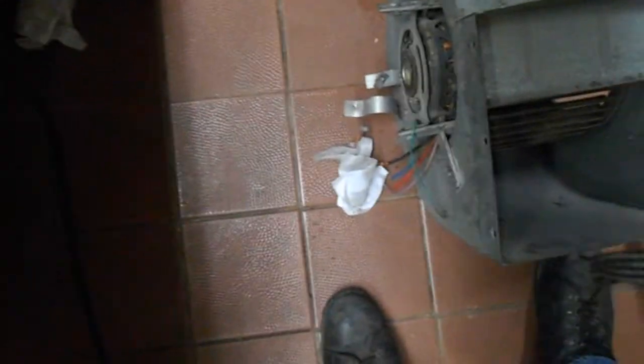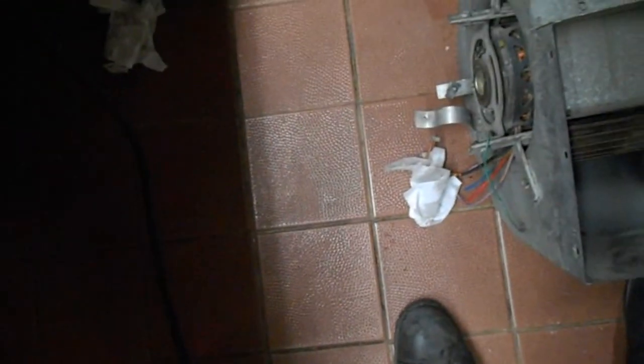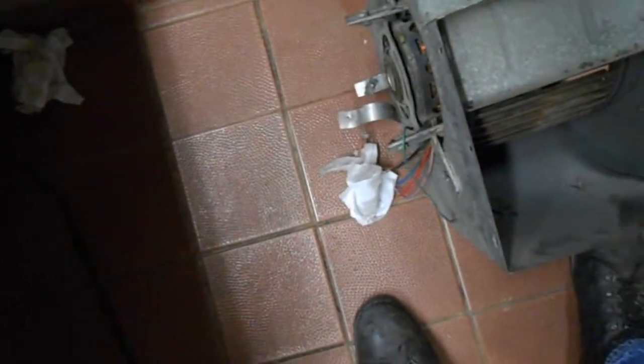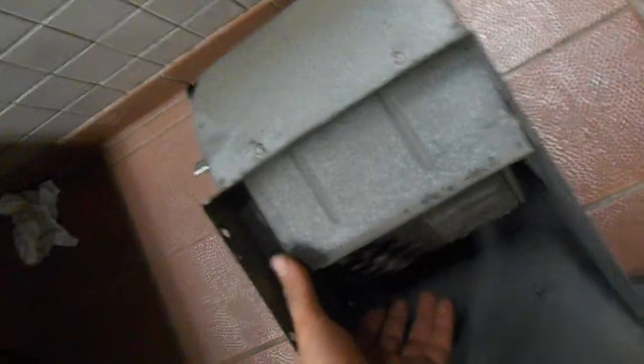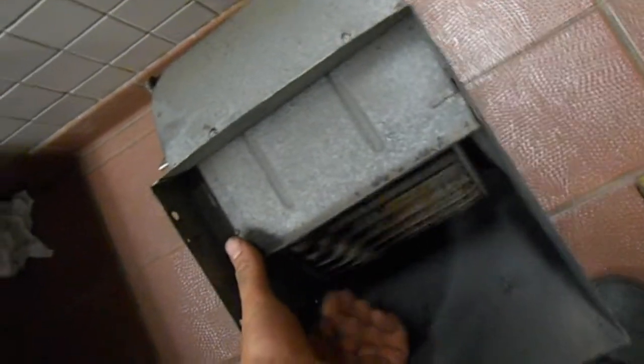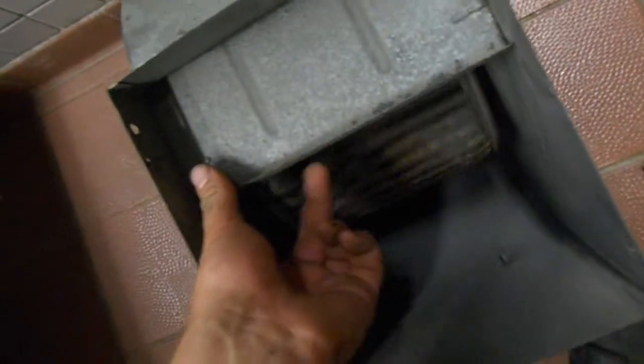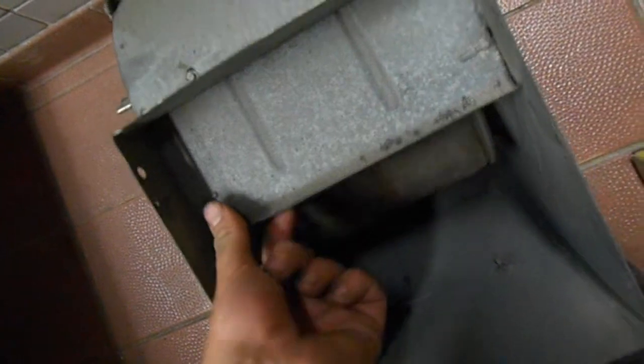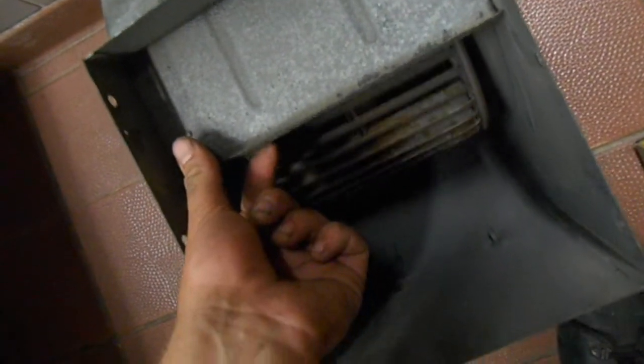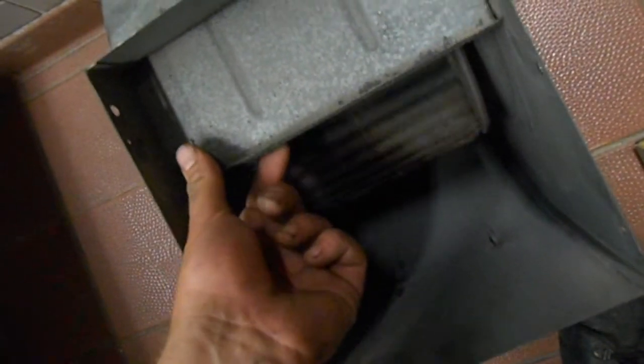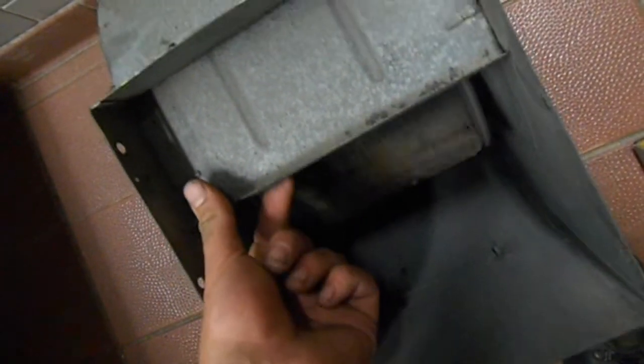So, this fan motor, it's not grounded either, which is kind of what I expected. Checked it with the megohmmeter even, and it's fine. But as you can see, the bearings have gone. So, this motor has mechanically failed. That should be spinning nice and freely right now.